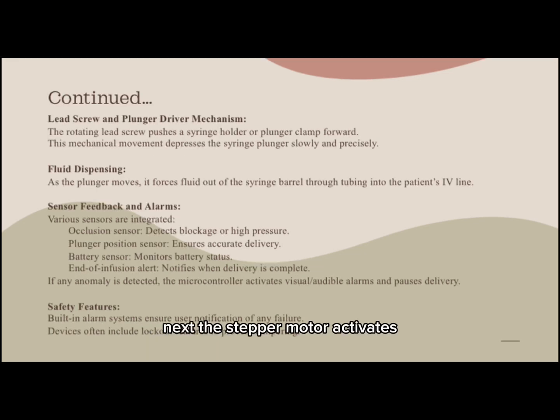Next, the stepper motor activates. It rotates a lead screw, which is a threaded rod that translates rotational motion into linear motion. The plunger driver, attached to the lead screw, pushes the plunger forward, expelling fluid at a slow, controlled, and constant rate. Sensors inside the pump continuously monitor parameters.